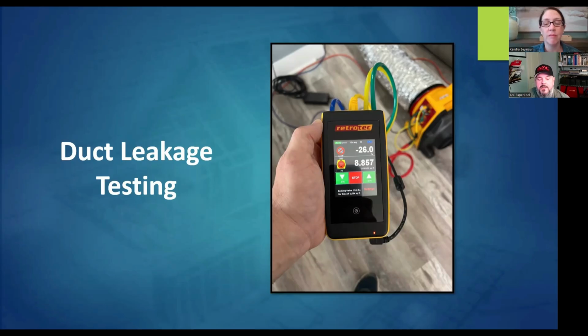Leaky return side, this is the negative side. This is going to cause filter bypass. You're going to be pulling unconditioned air from the attic, crawl space, wherever the system's sitting. This goes directly into the unit unfiltered, which causes microbial growth contamination pretty quickly. So once again, we always wonder, why do we have this major microbial growth issue in our AC systems? This is why. Because we're pulling unconditioned, unfiltered air directly into our unit where it's cold, dark, and wet. You tell me what's going to happen.